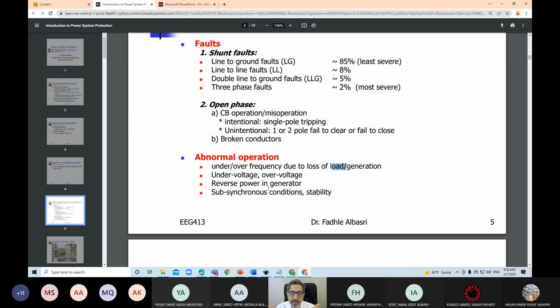In that situation, the active power flow will reverse. Instead of power generated to the system, the generator will now absorb power and act as a motor. And we need to detect this situation by using reverse power detection, a relay that detects that the power has reversed. This is not related to the control system. Subsynchronous resonance conditions, stability conditions, are all abnormal conditions, something called power swing conditions. These are abnormal conditions that the protection system also needs to detect, so that it takes proper actions.